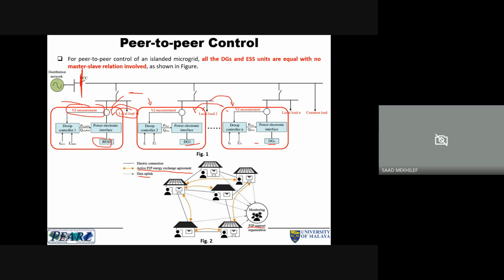In peer-to-peer control, it belongs to droop frequency regulation, so that allows some frequency and voltage deviations - we expect some deviation, especially in islanded mode. Compared to master-slave control, peer-to-peer control enables each DG and battery storage system to automatically participate in power output allocation, which facilitates plug-and-play functions.